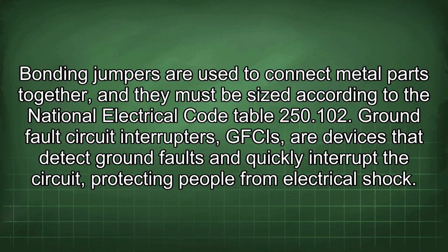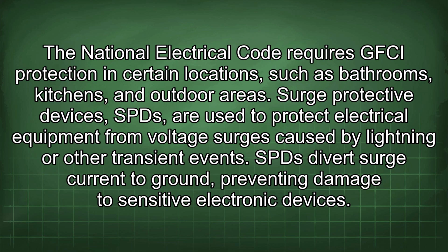electrical shock. The National Electrical Code requires GFCI protection in certain locations such as bathrooms, kitchens, and outdoor areas. Surge protective devices, SPDs, are used to protect electrical equipment from voltage surges caused by lightning or other transient events. SPDs divert surge current to ground, preventing damage to sensitive electronic devices.